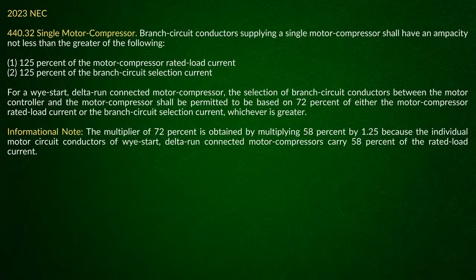So when you look at 440.32, this is where you get into your branch circuit conductors, and you've heard me say this, especially when we just got through doing the Journeyman layout. I said take all your motors at 100%, and the one motor that's the largest, you take at 125%. The same thing is going to happen here. You've got all your different motors, and if you have just a single motor compressor, you take it at 125%. Any additional motors, you take at 100%. I'm going to show that calculation here in just a minute.